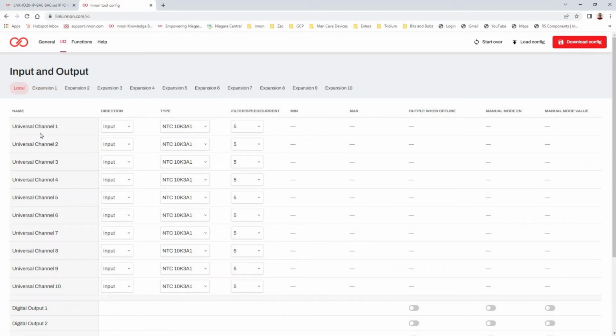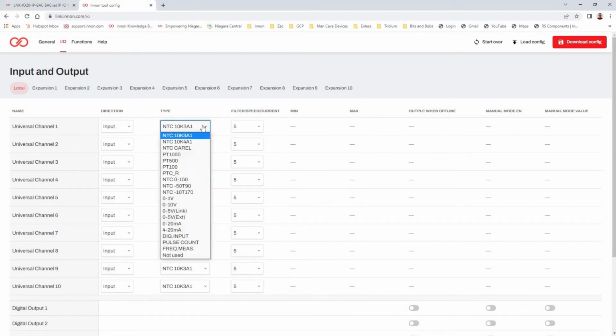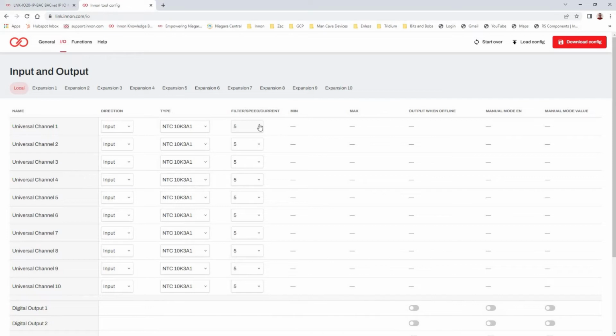So what have we got here? So on the universal channels, you can set up input or output. If you change it to an output, the types change obviously to the output specific types. When it's input, you've got a range of different thermistor type sensors, or active 0 to 10, 4 to 20 milliamp, or if you want it to be pulse count, digital input, all that kind of thing is catered for there. There's also a selection here for filter speed. This is context sensitive. With an analog input, you might want to filter it if it's say a static pressure in a duct or something. You might want to do more filtering on that and increase that number there. So it gives you some options there.